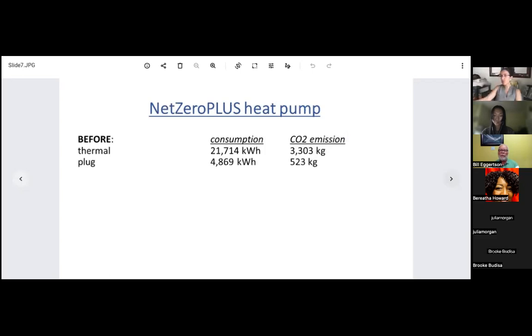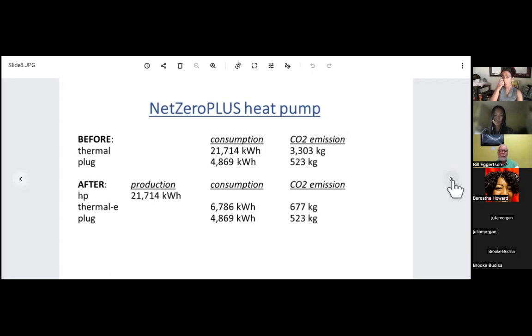In the average house, consumption was 21,000 kilowatt hours for thermal, emitting 3.3 tons, and plug load was 4,800 kilowatt hours. If you install a net zero heat pump, it produces all of the thermal, 21,000 kilowatt hours a year. The heat pump requires electricity to run the compressor, and at absolute maximum, with a 3.2 coefficient of performance, you'd need at most 6,700 kilowatt hours.